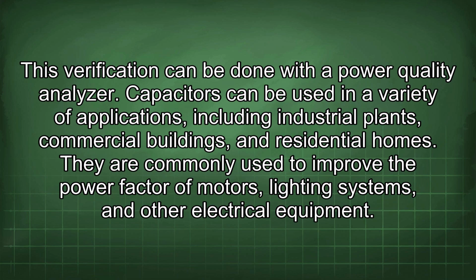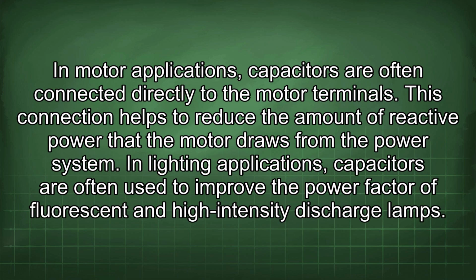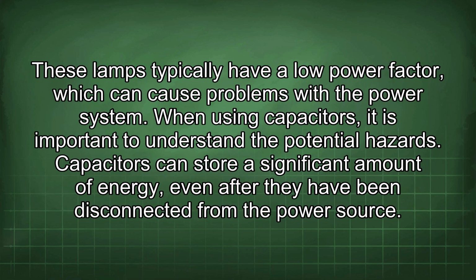They are commonly used to improve the power factor of motors, lighting systems, and other electrical equipment. In motor applications, capacitors are often connected directly to the motor terminals. This connection helps to reduce the amount of reactive power that the motor draws from the power system. In lighting applications, capacitors are often used to improve the power factor of fluorescent and high-intensity discharge lamps. These lamps typically have a low power factor, which can cause problems with the power system.